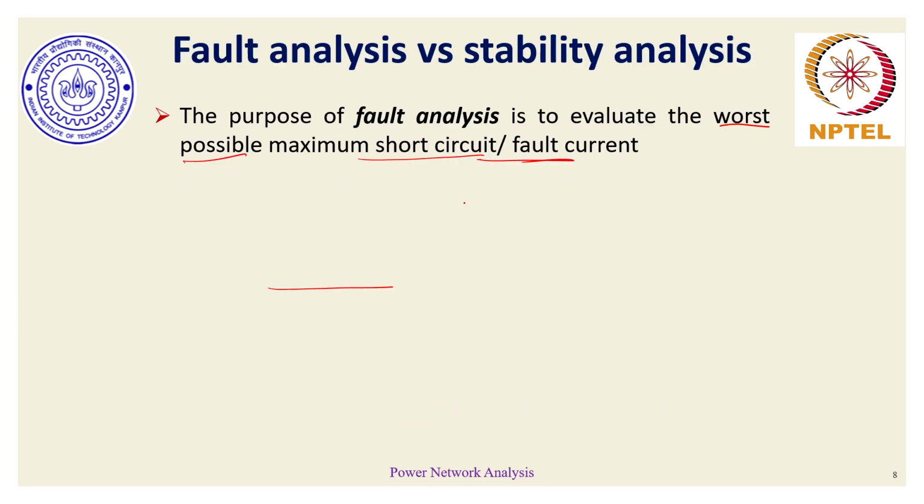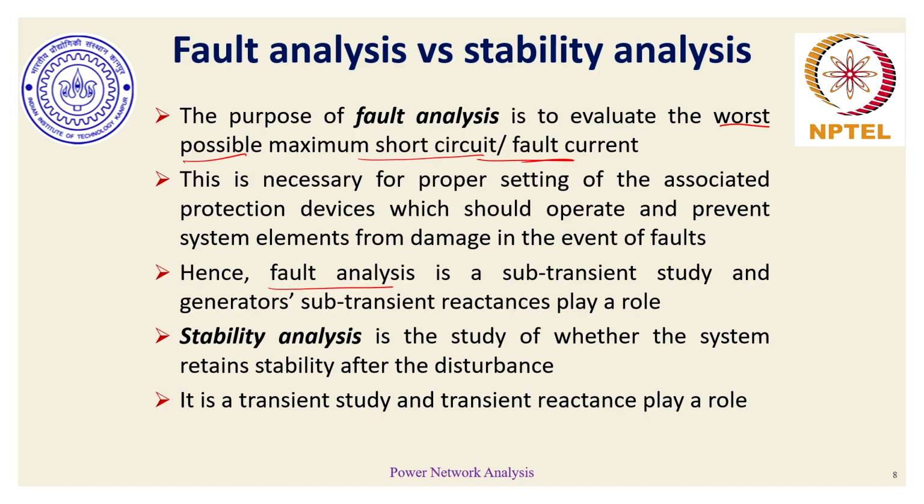And those stable and unstable conditions are what would be our focus of study in the stability analysis. And hence, in that stability analysis, the XD dash value would be important. For fault analysis, XD double dash values are important.